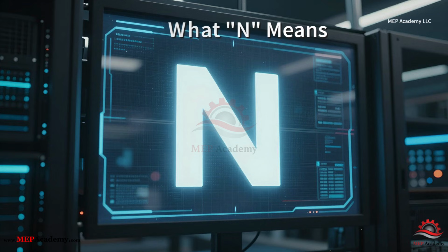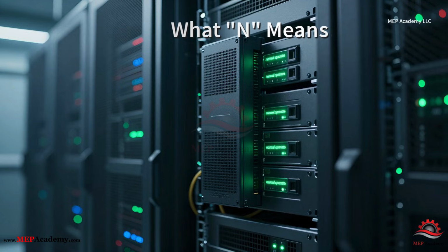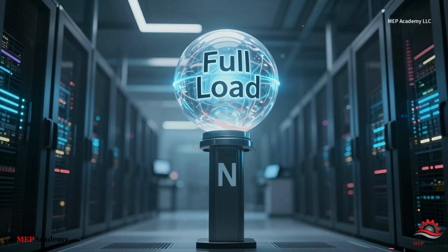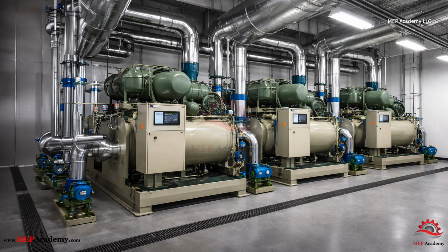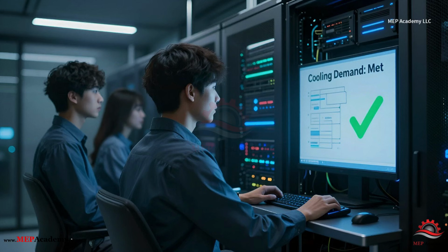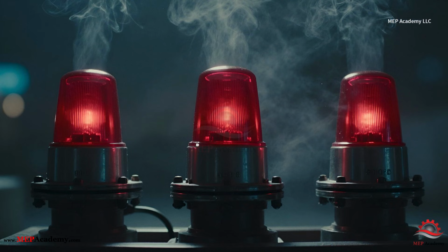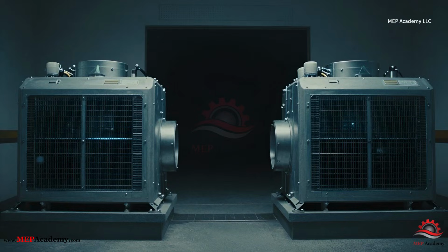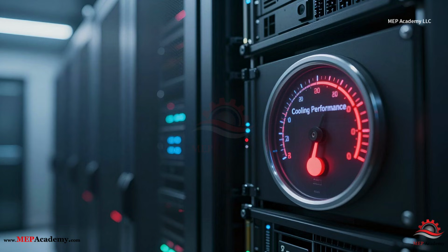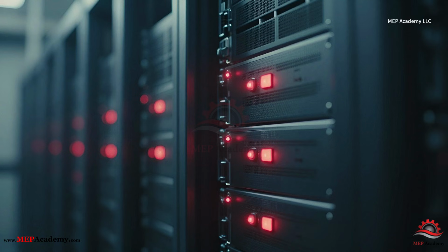What N means. The letter N represents the amount of equipment required to operate normally. In other words, N is the minimum number of systems needed to support the full load. For example, imagine a data center requires 3 chillers to remove all the heat produced by the servers. In this case, 3 chillers equals N. If all 3 chillers are running, the cooling demand is satisfied. But if one chiller fails, there is no backup capacity. Cooling performance would drop and the servers could begin overheating.